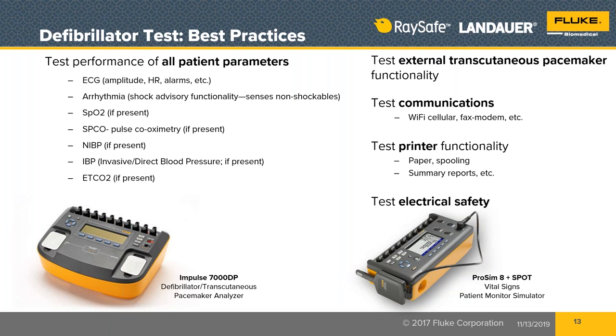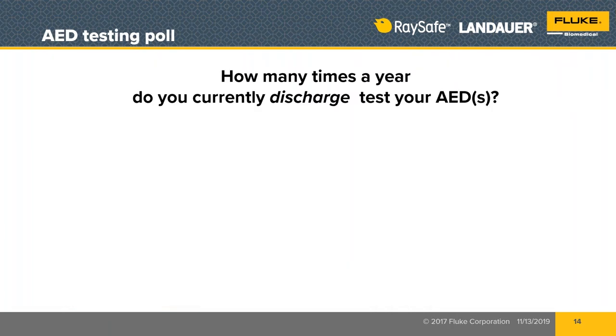And printer functionality, because we never make measurements off the display screen of a defibrillator or a patient monitor. We run a strip and we make measurements on the strip chart paper when we're looking at the arrhythmia of the patient. And the summary reports also are printed out using that printer functionality. And oh, by the way, electrical safety testing. We have a whole separate webinar about electrical safety testing, and I'll just refer you to the archive either on TechNation or also on the Fluke Biomedical website, where you can learn a little bit more about electrical safety. So you want to make sure you're doing all of the testing that's required.